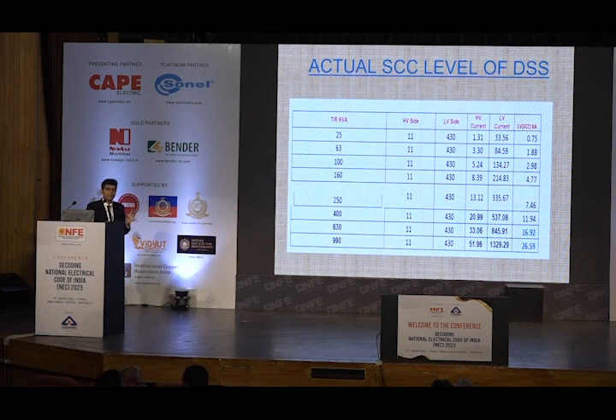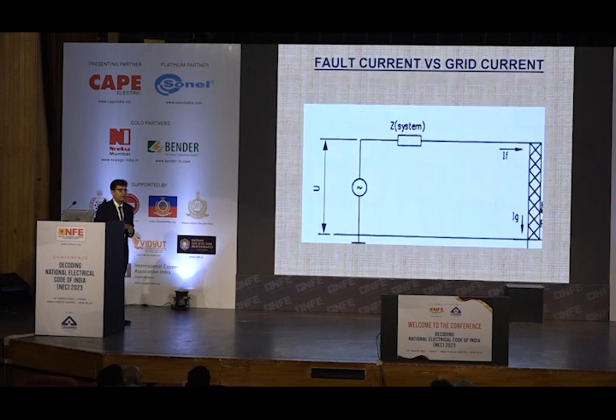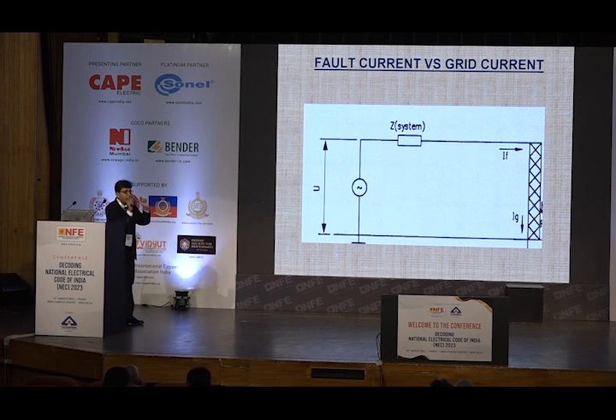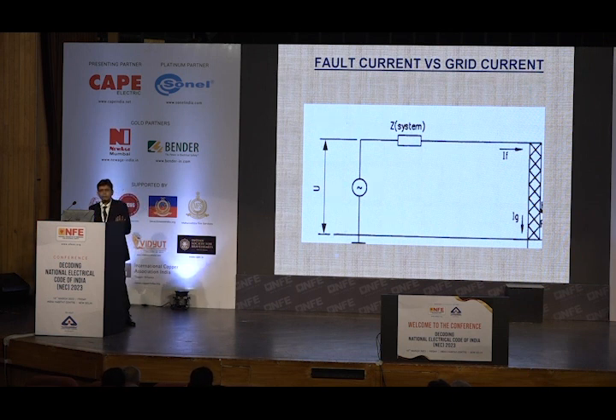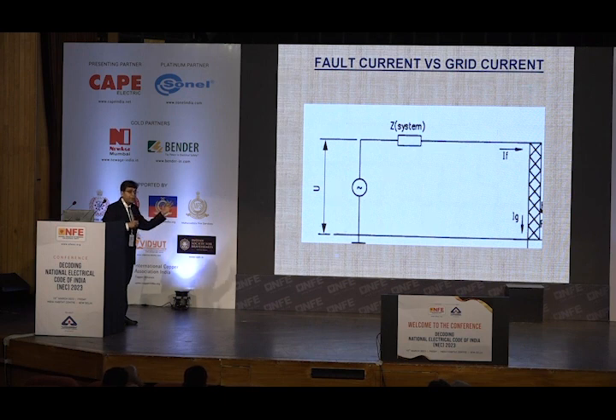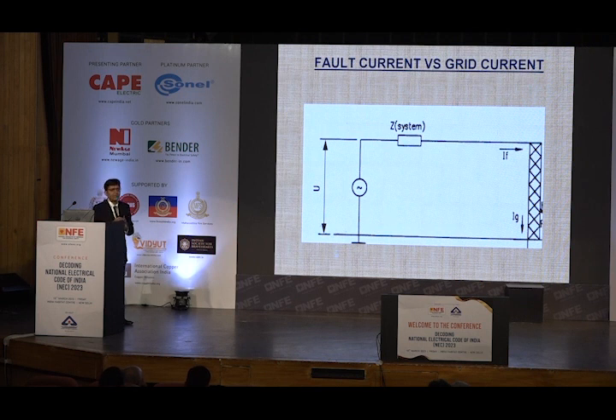This is one side of the story. Here comes the second side, which is called the split factor. Whenever a fault happens in the system, all that fault current never uses Mother Earth to go back to the source. It takes help of your overhead wires, the armor, and the screen of the cable to go back to the source. But every time we design based on 40 kiloampere, 63 kiloampere, 50 kiloampere, 31.5 kiloampere, without considering the impact of this split factor in the system. This is the second good aspect to be considered by all electrical engineers while designing an earthing system.